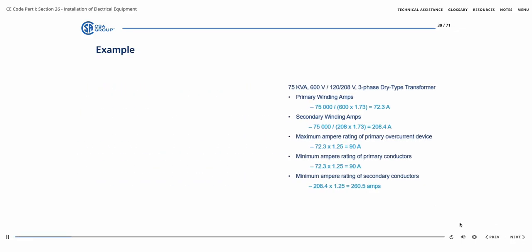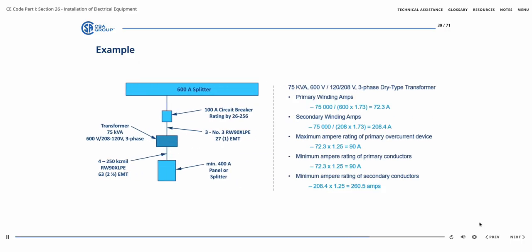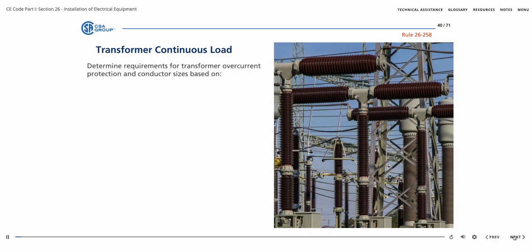The first figure on the screen shows steps for determining winding amps, along with the formulas for conductor ampacity ratings. The second shows the results of the calculations from Figure 1. The requirements for the purpose of transformer overcurrent protection and conductor sizes are discussed in Rule 26-258. The continuous load as determined from the calculated load connected to the transformer's secondary shall not exceed the values specified in Rule 8-104, Subrule 5 or Subrule 6, when determining compliance with the requirements of Rule 8-104 for continuous loads.